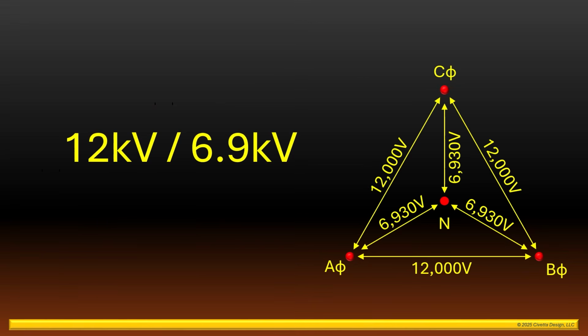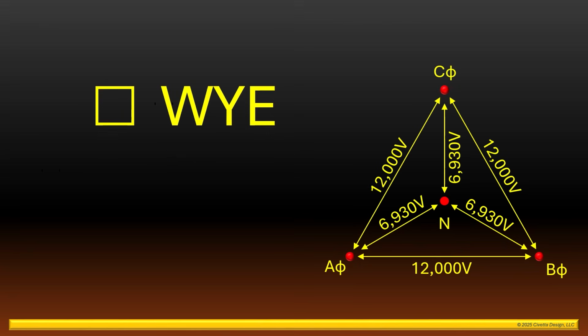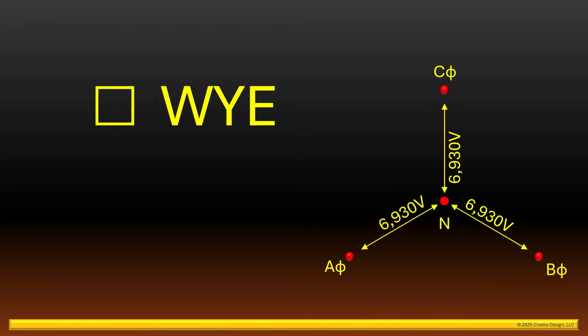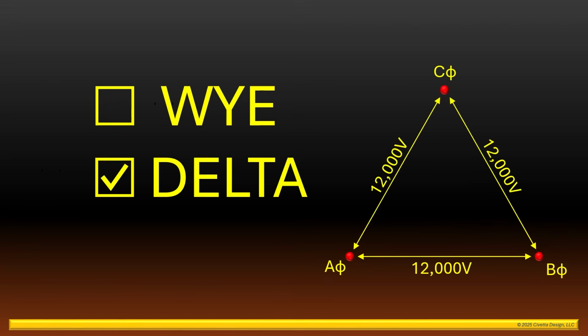Three-phase transformer banks can be connected to the primary system in one of two ways. When a neutral is present, transformers can be connected to the primary high-voltage conductors in a Y configuration, utilizing the phase-to-neutral voltage of 6.9 kV. When a neutral is not available, the transformer bank must be connected in a delta configuration, which utilizes the full 12 kV phase-to-phase voltage. We'll also show how the secondary side of the transformer bank can be connected in a delta configuration and the secondary voltages that are created.